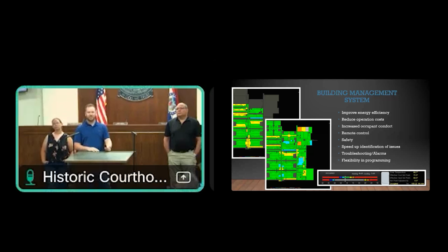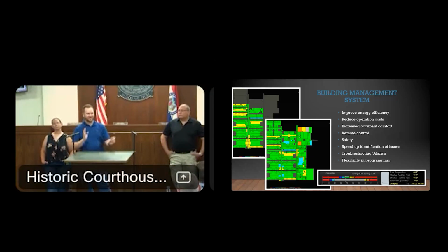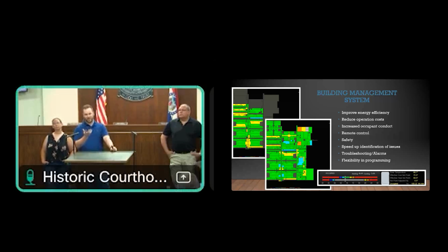This is pretty much the brains of the building as far as the HVAC system goes. At the jail, we had an issue where, when we were testing our generators weekly, the exhaust from the generators was getting sucked right back into the sheriff's building and causing all sorts of headaches. With our control system, we were able to program it so that the units on the sheriff's office would close down and not bring in any outside air while the generators were running. That alleviated our problem, and we didn't have to change anything with the building itself. That's just one example of the capabilities of our building management system, and that system is campus-wide too.